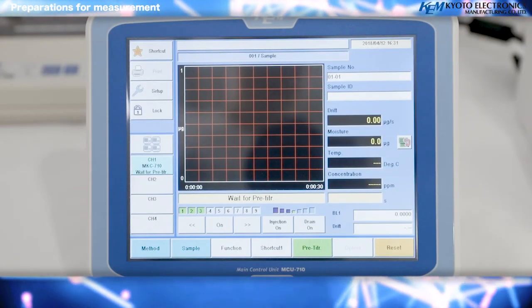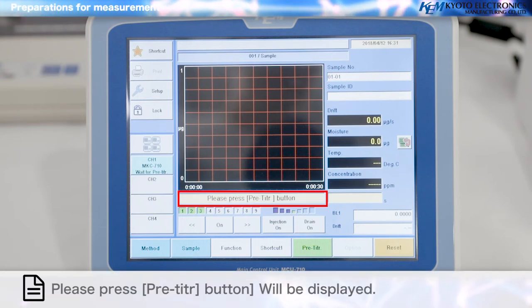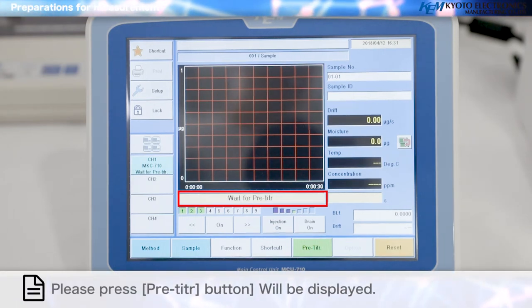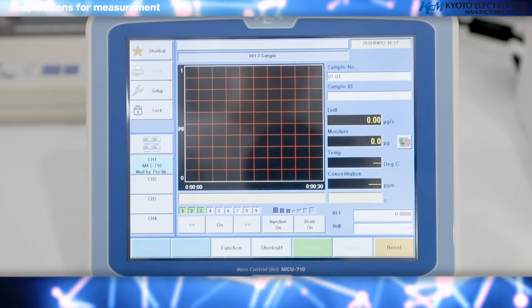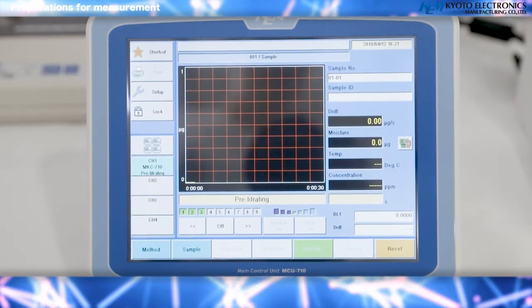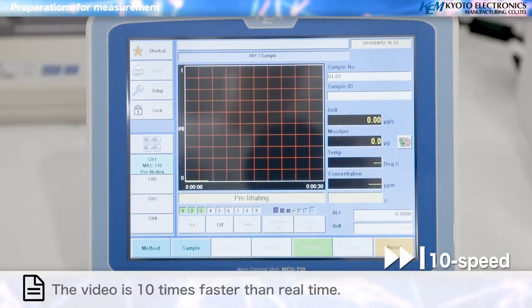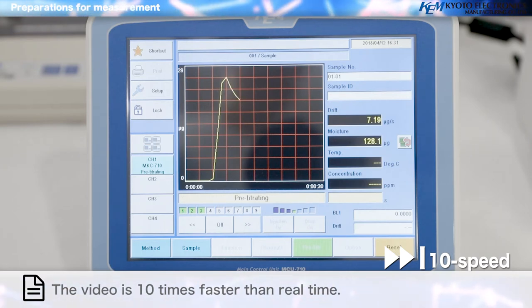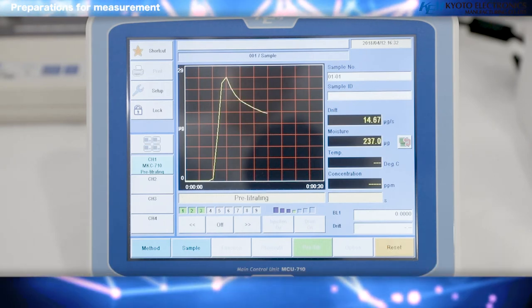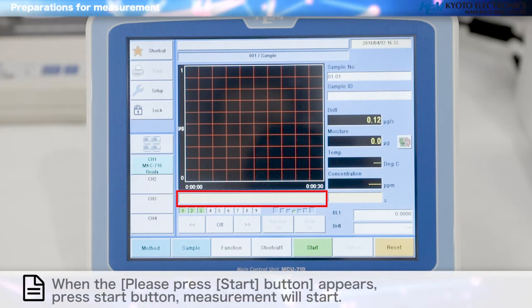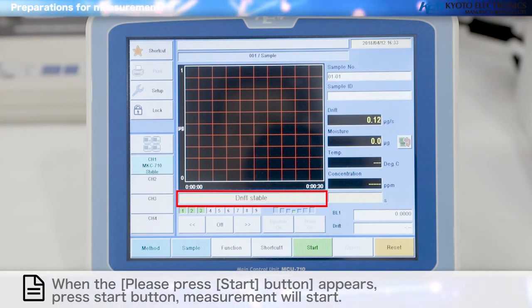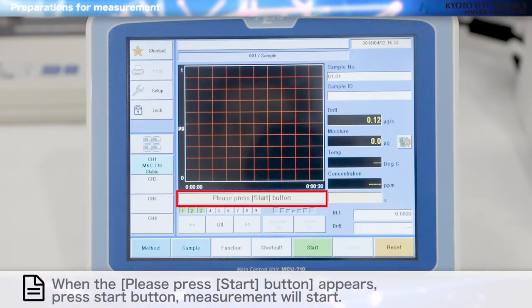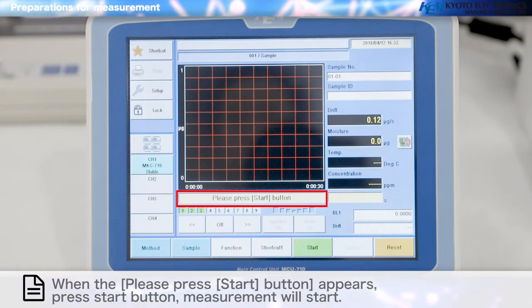Preparations for measurement: first carry out the pre-titration. Press the Pre-Titration button — pre-titration will begin. When the pre-titration is finished, wait until the drift value stabilizes.